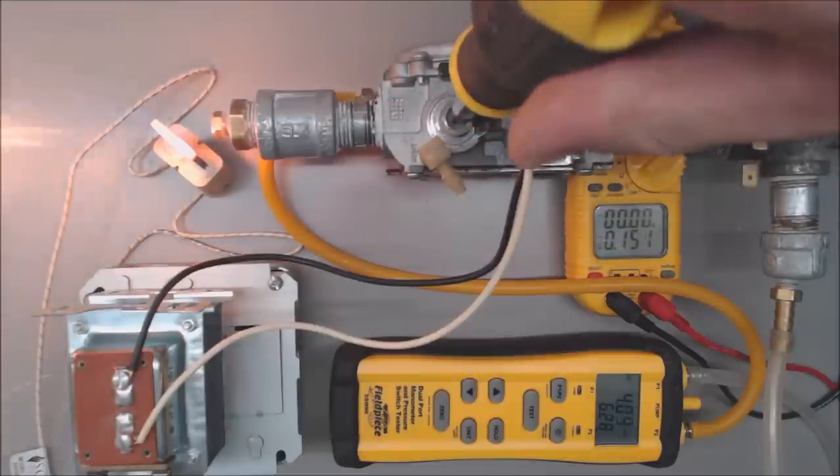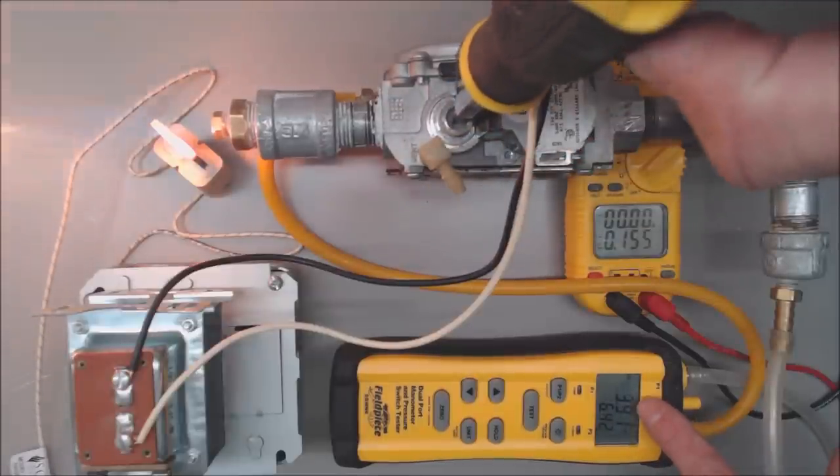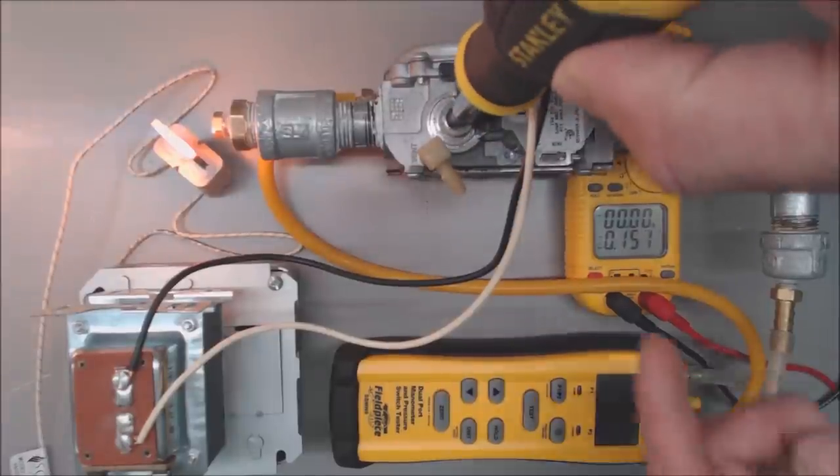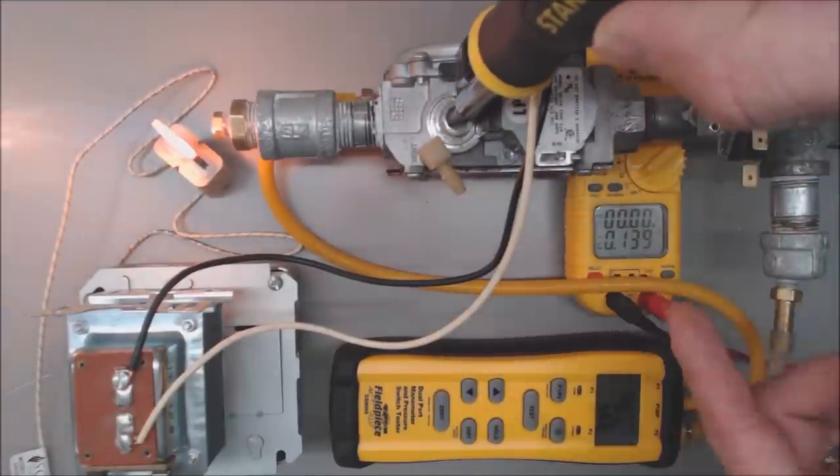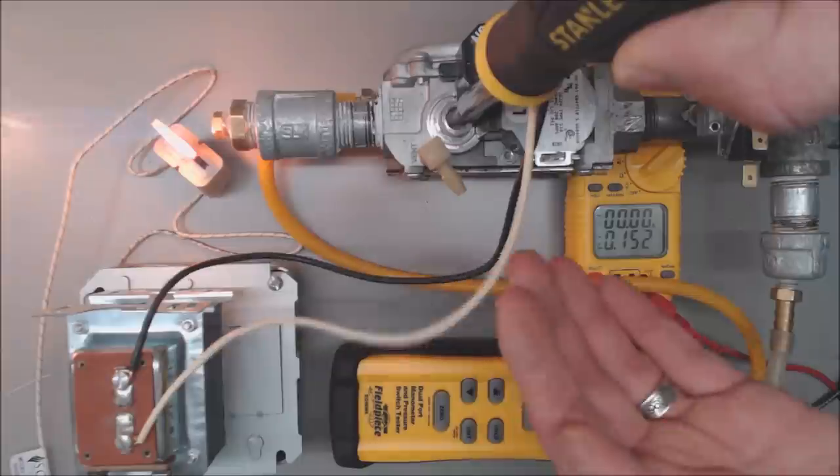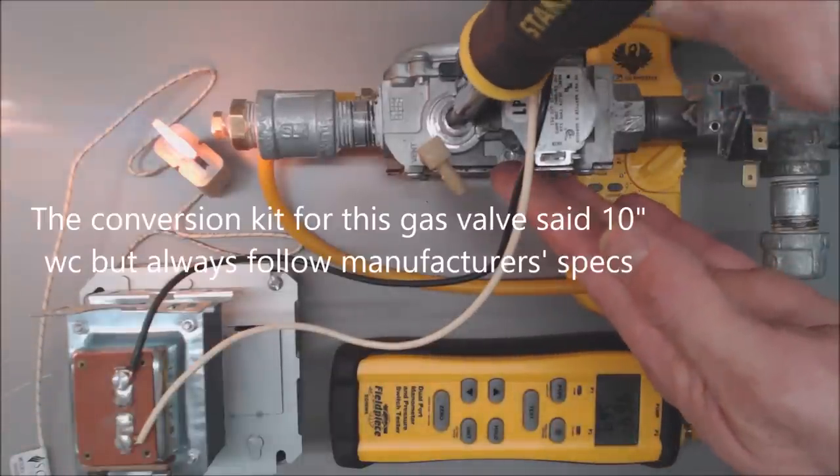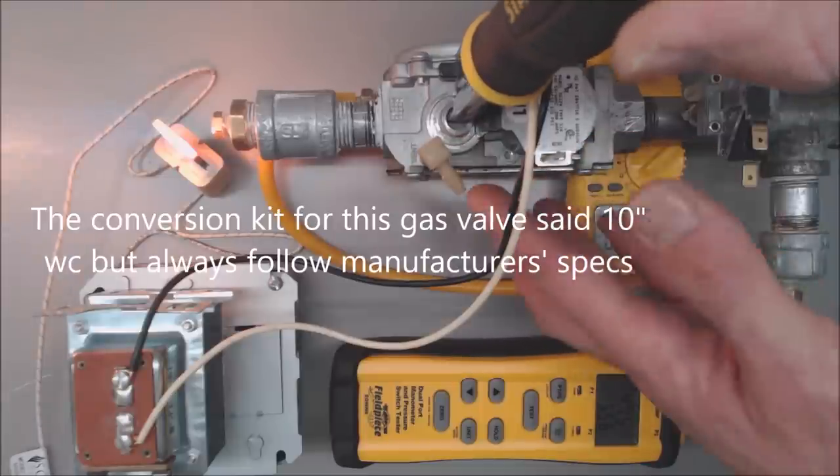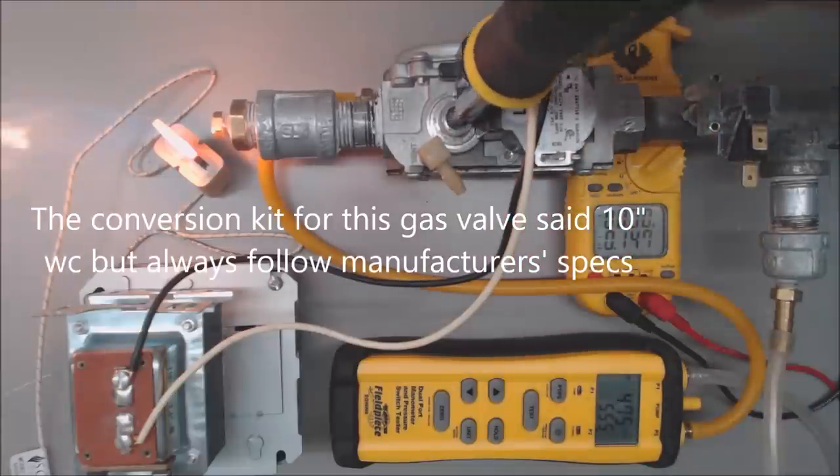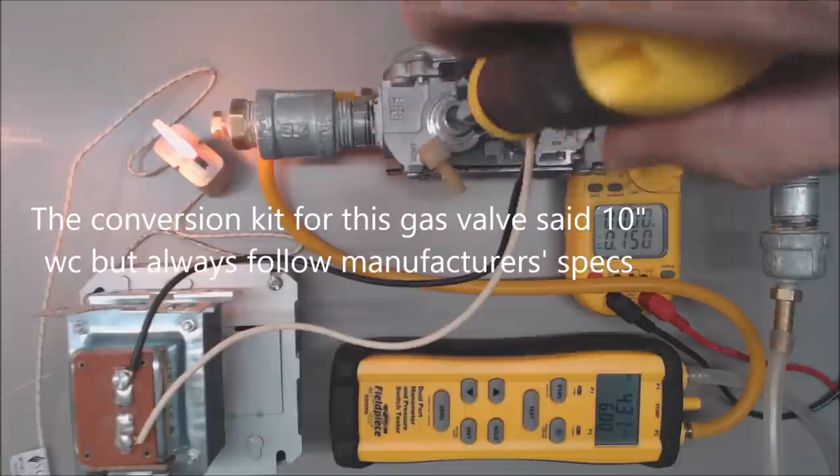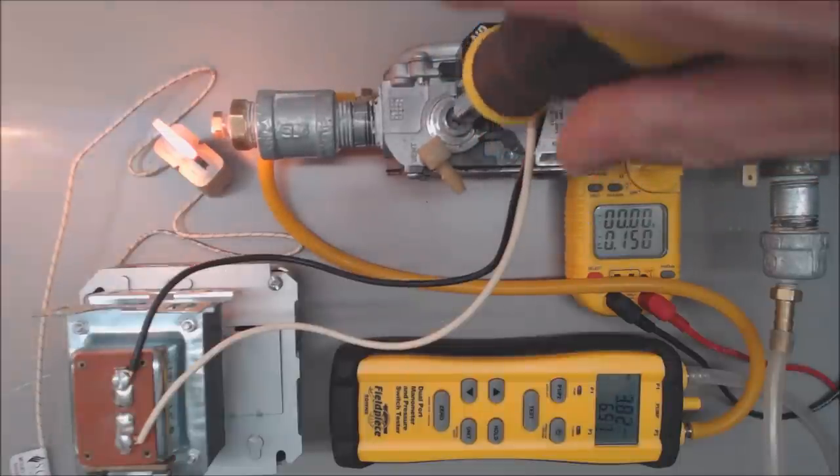If you keep turning it clockwise you're going to increase the water column reading. As you decrease, the reading will follow as well. So you want to turn this clockwise until this reaches 10 inch water column, or basically while you're reading your combustion analysis you want to make sure that you get that as accurate as possible and then set it accordingly very close to 10 inch water column, but based on your combustion analysis. But that's how it's done.